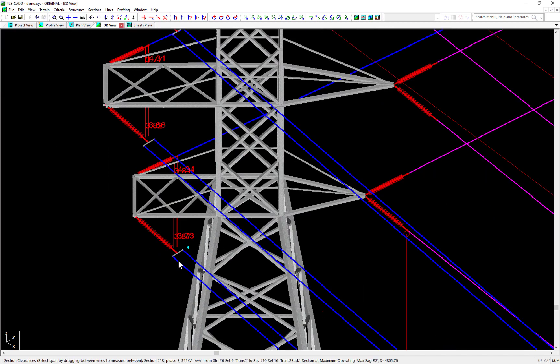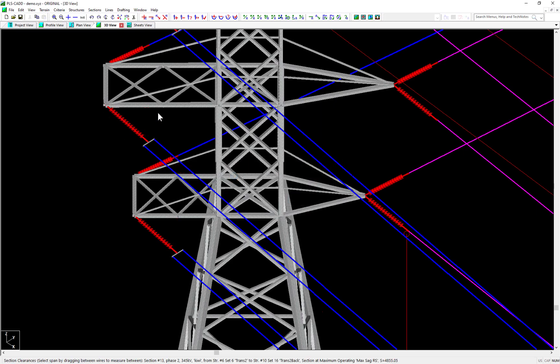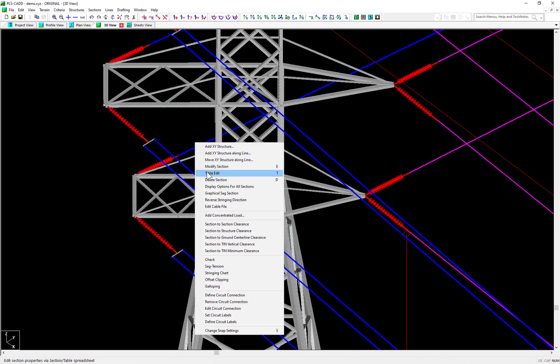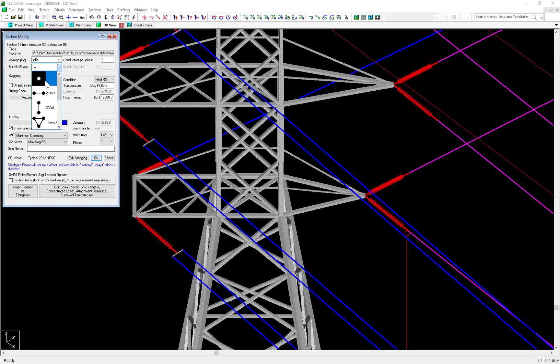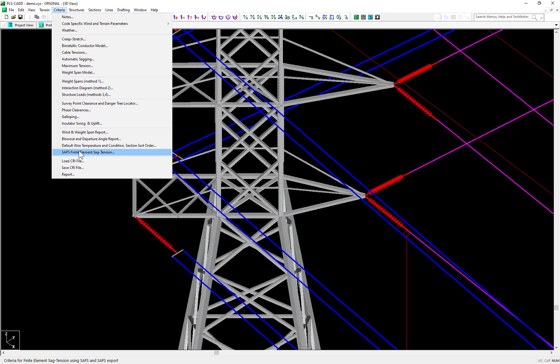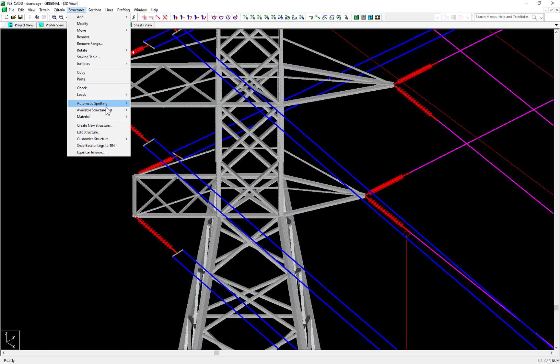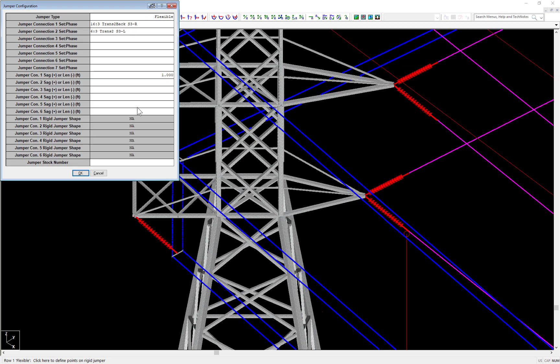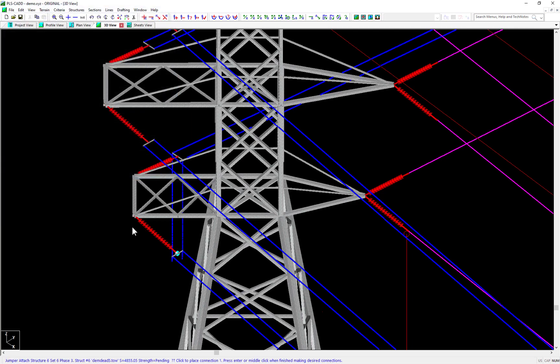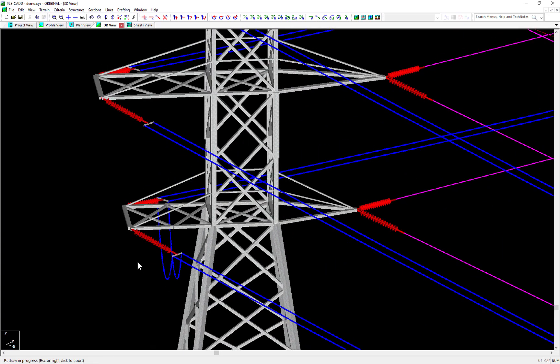And these features even work on jumpers as well. If I configure the backspan to have the same conductor geometry, then switch on jumpers, then create a jumper at this structure 6, you can see that jumpers will also show the subconductor geometry. And it too will be accounted for in clearance checks both wire to wire and wire to structure.